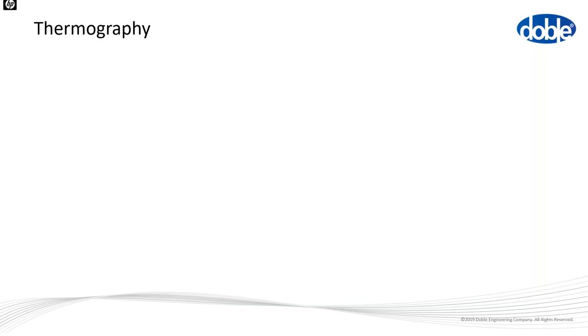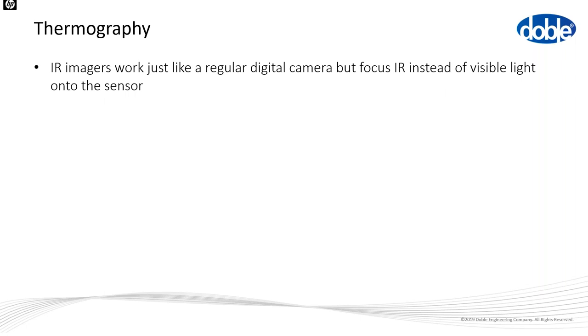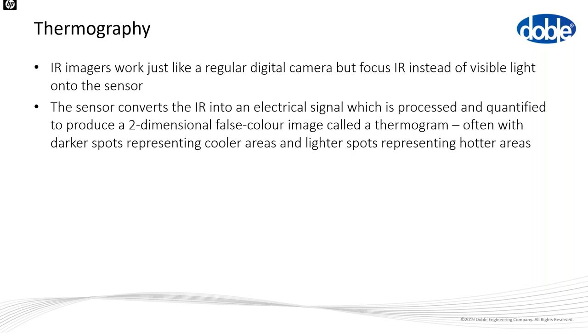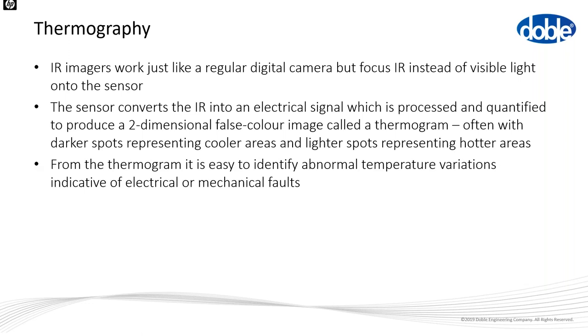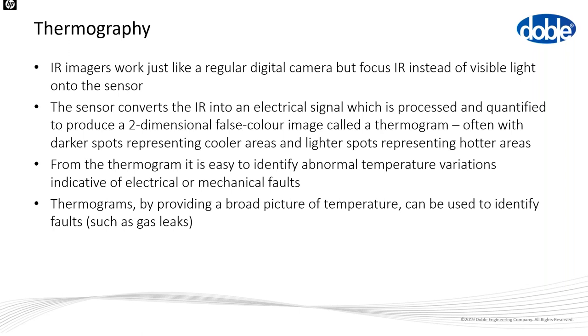We can also use an infrared imager for thermography. It works just like a regular digital camera but focuses on the infrared spectrum instead of visible light. A sensor converts the infrared into an electrical signal, which is converted into a false-colour image called a thermogram — darker colours represent cooler areas and light spots represent hotter areas. From the thermogram we can easily identify abnormal temperature variations indicative of electrical or mechanical faults, such as gas leaks or poor cooling in a particular motor where one part runs hotter than the rest.